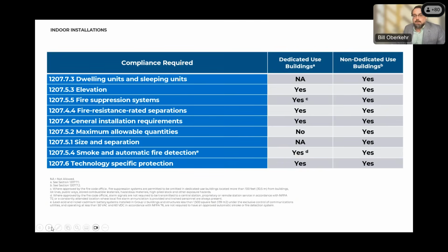And we're going to go through very quickly what some indoor installations are. There's just not that much to say here. We have a similar table to the outdoor. We have two types of indoor installations in the code. One is a dedicated use building, which is exactly what it sounds like, a building that is dedicated to the use of batteries. So a few things in the code are not going to make sense there. For instance, dwelling and sleeping units: if they're dedicated to the use of batteries, you're not going to have a dwelling or sleeping unit. Size and separation, you don't really need separation if that's really all that's going to be in the building. And then a non-dedicated use building is any other type of building. So a house, a hospital, a commercial industrial facility, anything else. Next slide, please.